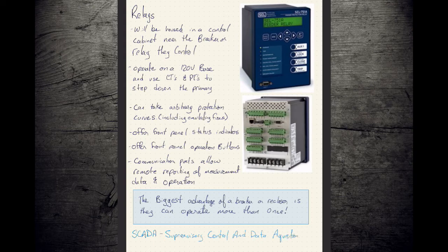These are systems that get used in utility control rooms, and they allow a remote operator to both see the currents and voltages at that point in real time, but they also allow the operator to open and close these units from the control room, so that the control room operator has the ability not just to see, but to influence power flows through the network, which has some pretty significant implications for field staff like yourselves.